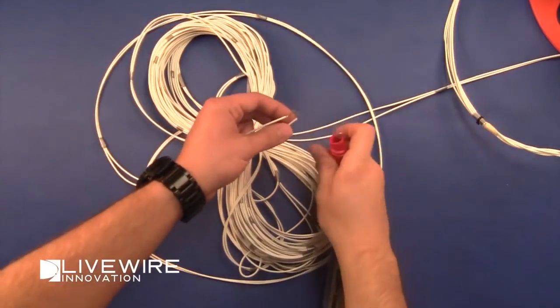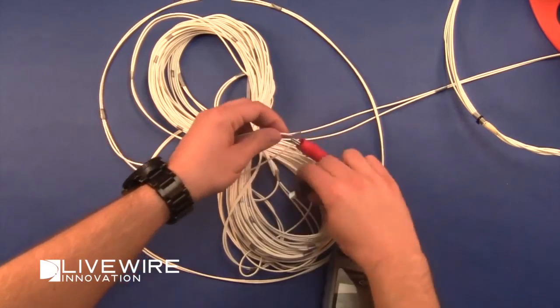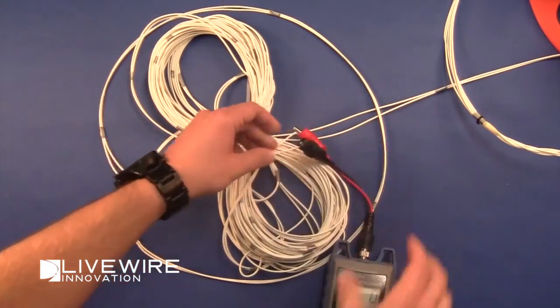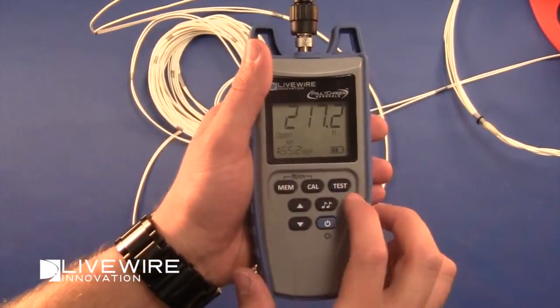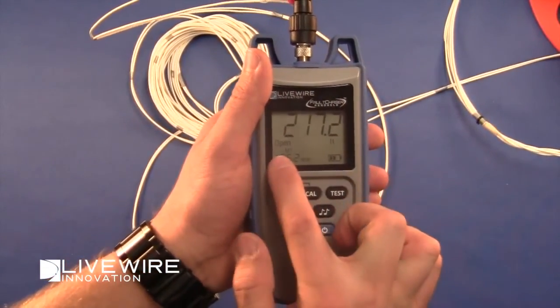In this first example, we'll be finding the location of the open circuit or break in this discrete bundle. We know that the NVP value is 65.2, which we have already set on the Fault Chaser. It tells us that the open is at 217 feet.